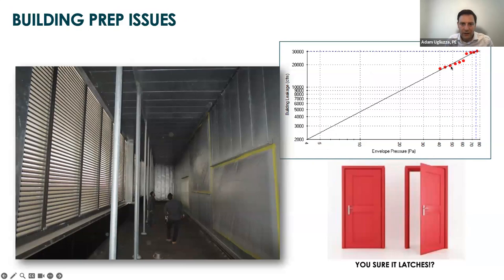You're humming along. Your test points are following the linear path, right in line. There's no deviation from it. All of a sudden we're stepping up. That's indicating something happened. Something opened up, whether it was a door, whether it was building prep. In this case, it was building prep. It was, and of course it was where we couldn't reach. It was where the plastic unsealed from the top of the damper.